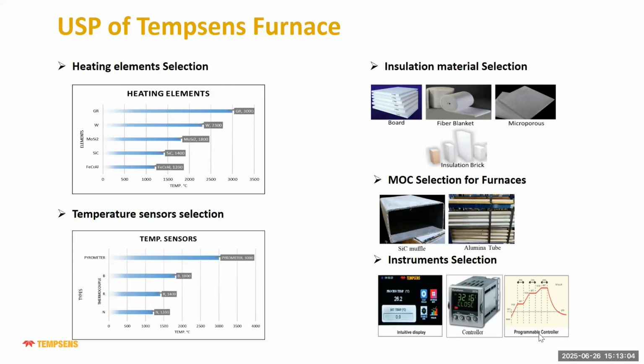You can see the elements: FeCrAl can work up to 1200, silicon carbide 1400, MoSi2 to 1800, tungsten 2300 degrees centigrade, and graphite 3000 degrees centigrade heating element. And for temperature sensors, N type can be used up to 1200 degrees centigrade, R type 1400, B type 1800, and pyrometer 3000 degrees centigrade. Then we have different types of insulation, like ceramic fiber board with blanket, microporous board, insulation brick, muffles, with different types of panels like controller, intuitive display, programmable controller, like that.